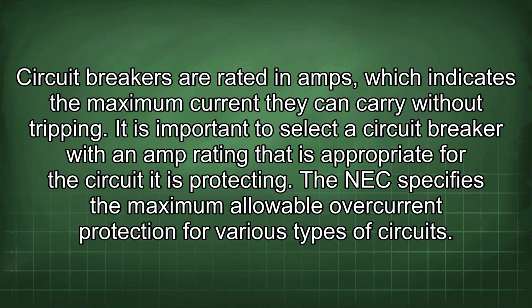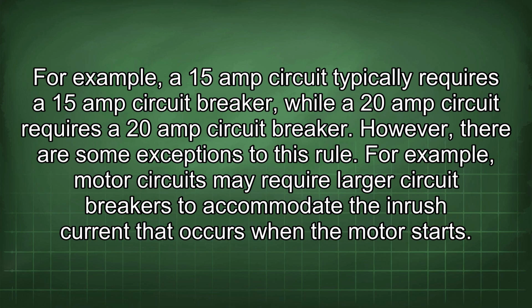It is important to select a circuit breaker with an amp rating that is appropriate for the circuit it is protecting. The NEC specifies the maximum allowable overcurrent protection for various types of circuits. For example, a 15 amp circuit typically requires a 15 amp circuit breaker, while a 20 amp circuit requires a 20 amp circuit breaker. However, there are some exceptions to this rule. For example, motor circuits may require larger circuit breakers to accommodate the inrush current that occurs when the motor starts.